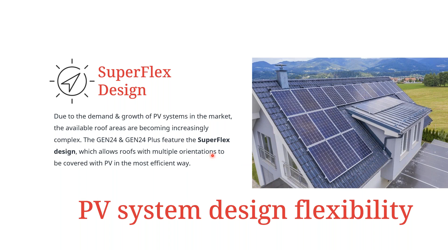And in this case, when you look at the flexibility that we are offering with the two inverters, whether the Primo or the Symo version of it, we have the two MPPTs. So with the two MPPTs, you can have two different orientations or a maximum of 3 in some cases. And because also of the broad input voltage, as we talked about, starting from 80 to 1000 volts for the Symo version and 65 to 600 volts for the Primo version, you can connect some modules in different orientations, just like this example given here. So you can have an east-western system orientation with 10 modules each. And then if you have a carport, for example, you could have a short string there that has only 3 modules, and you're able to connect this and pair it up also with the same Gen24 inverter.